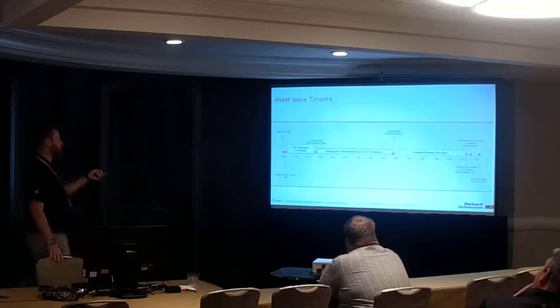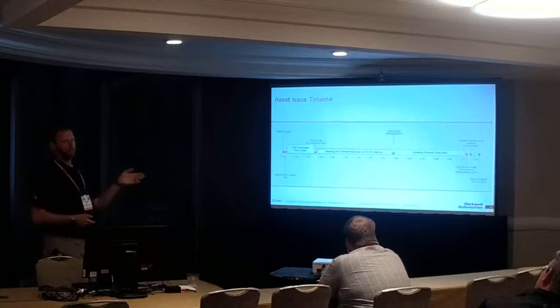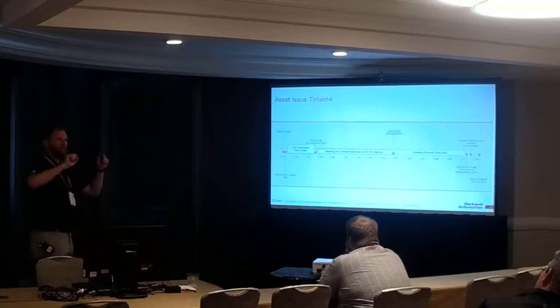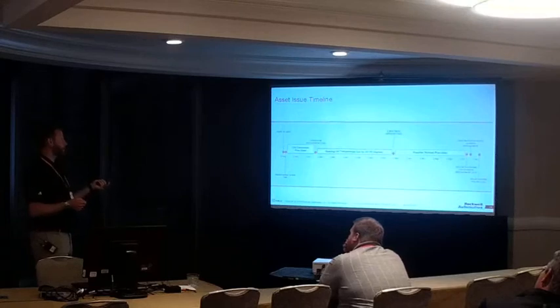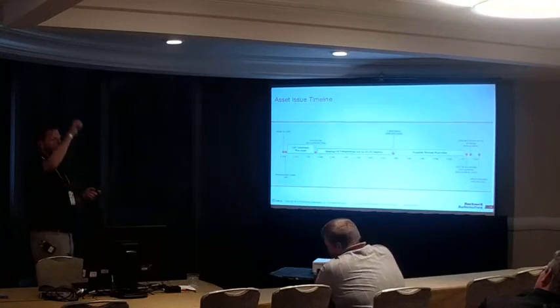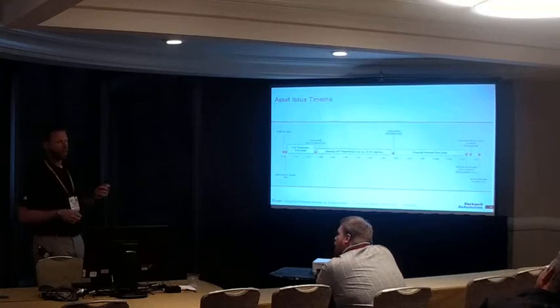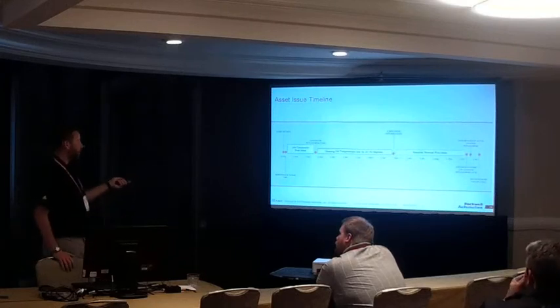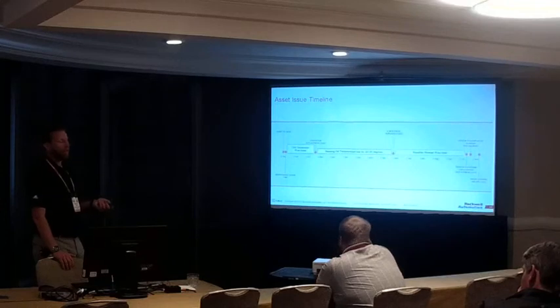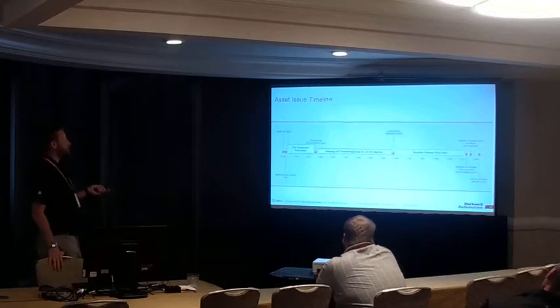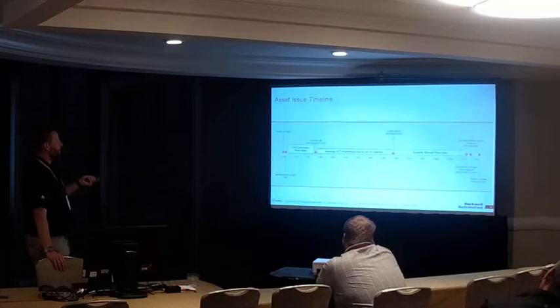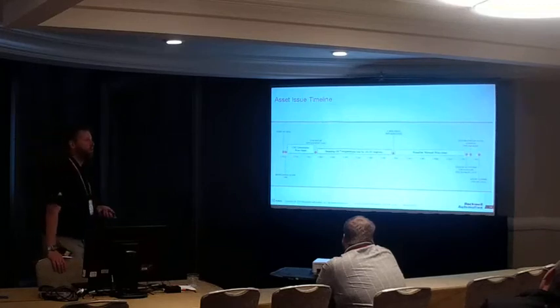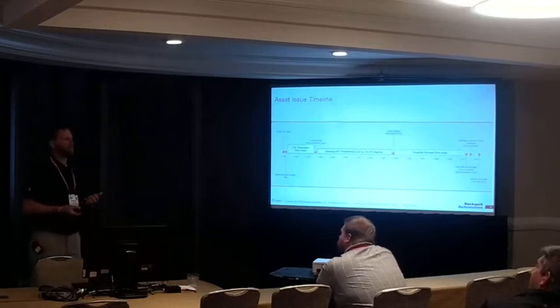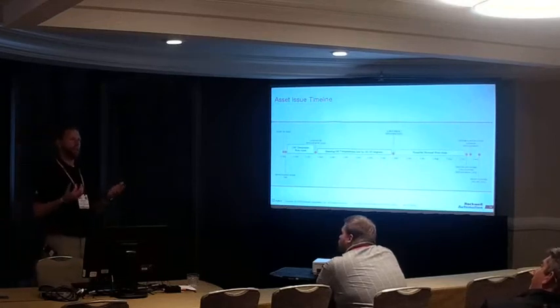Okay, now the temperature lowered itself, or lowered gradually, so operators didn't notice it. And they're also not looking at each individual parameter and necessarily trained to know that bearing temperature. They're looking for spikes, or significant quick acting sags, and they're not looking for a gradual decline and then flatline. So if you have any mechanical engineering experience, or you've ever worked on a car, the temperature being 30 degrees lower than normal is not good. Lower temperature, higher viscosity, higher friction.